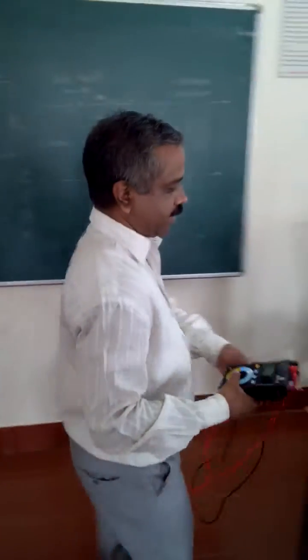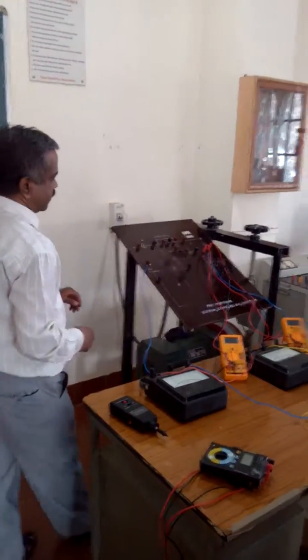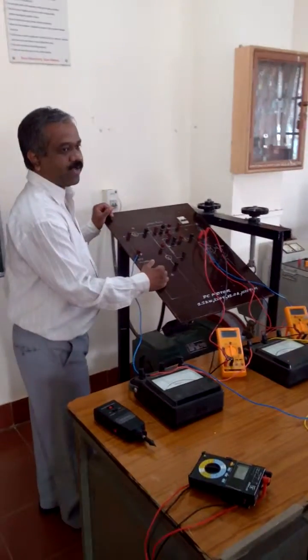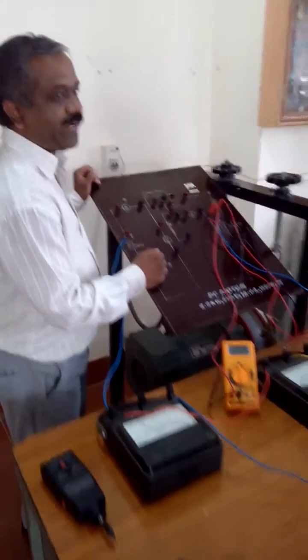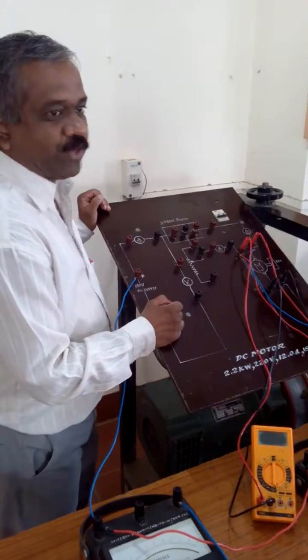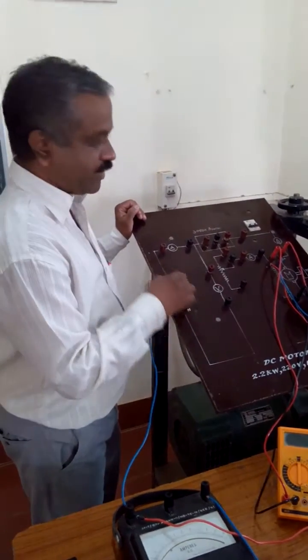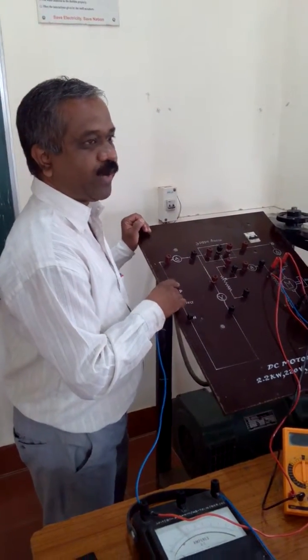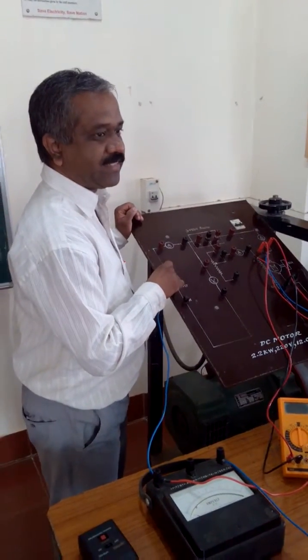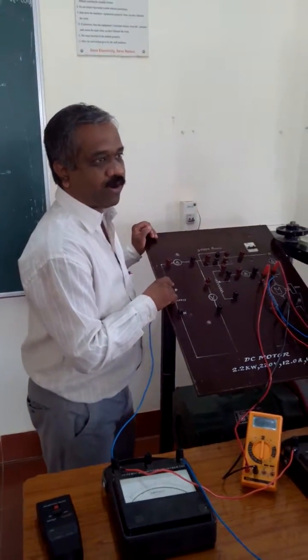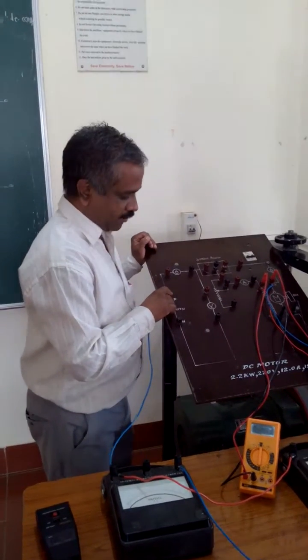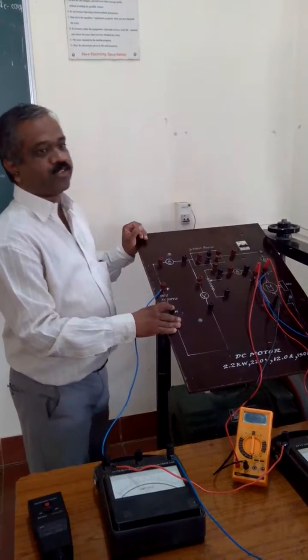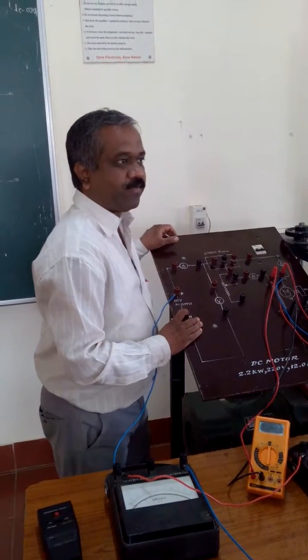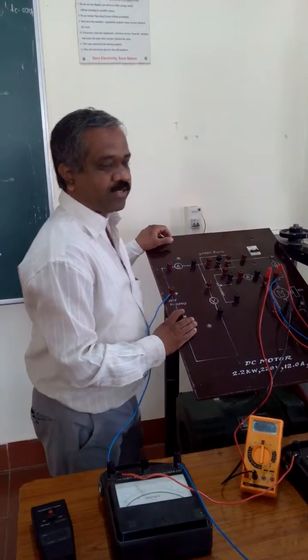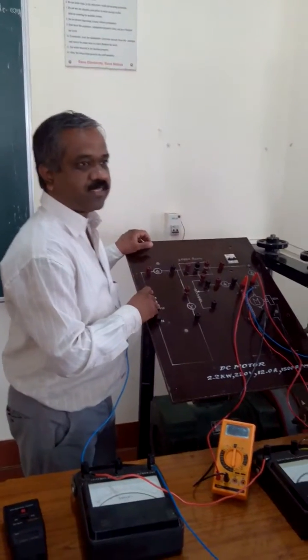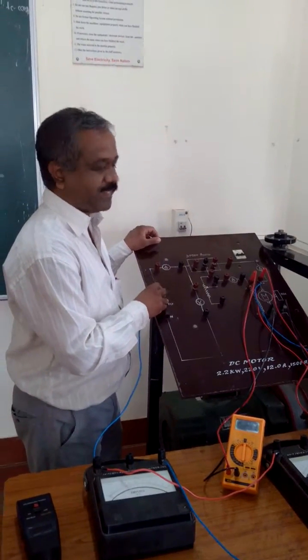Now in DC supply, the neutral which we are using is for DC, it is from a DC rectifier. So there are less chances of getting shock. Now what do you mean by shock? When you connect to the phase, that time current will flow through your body. Your body will act as a resistance, and because of I square R you will get a shock. That is in case of AC. But here in case of DC, neutral is isolated. So here less chances of getting shock. But better take precautions and don't touch the positive voltage of the DC supply.